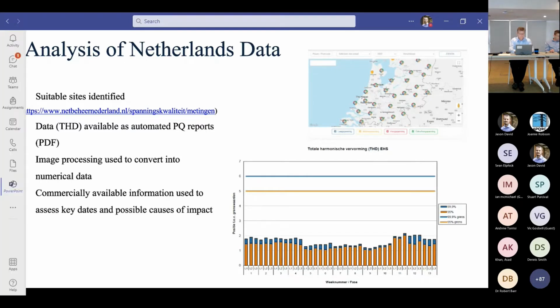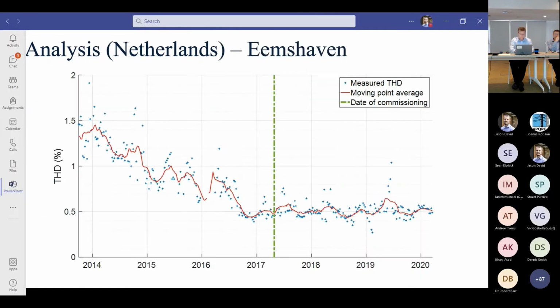As mentioned, the sites were identified based on available information of large offshore wind farms being connected to the network. These sites were analysed and the trends were defined. For the first site analysed, which was a substation in Eemshaven, we see a few things, the first being actual seasonal peaks and troughs. In the European summer, we tend to see a reduction in overall THD, or the trend of THD, which picks up towards the end of the year, after which we see these natural trends occur.